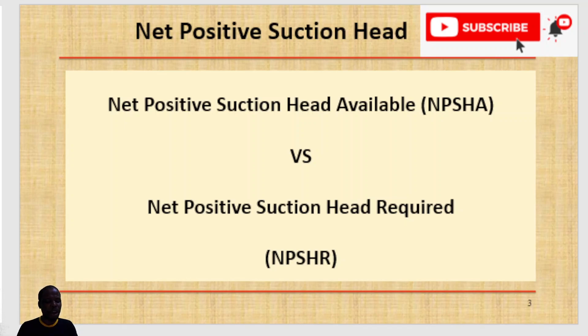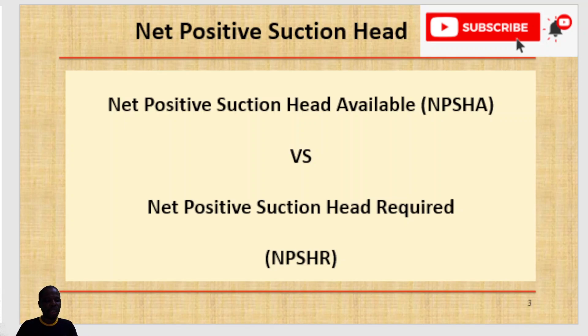For cavitation-free operation, the NPSHA must equal or exceed the NPSHr at the desired capacity. You don't want to be the engineer responsible for installing a noisy, damaged pump. It is very critical to get the NPSHr value from the pump manufacturer and ensure that your NPSHA will be adequate to cover that requirement.